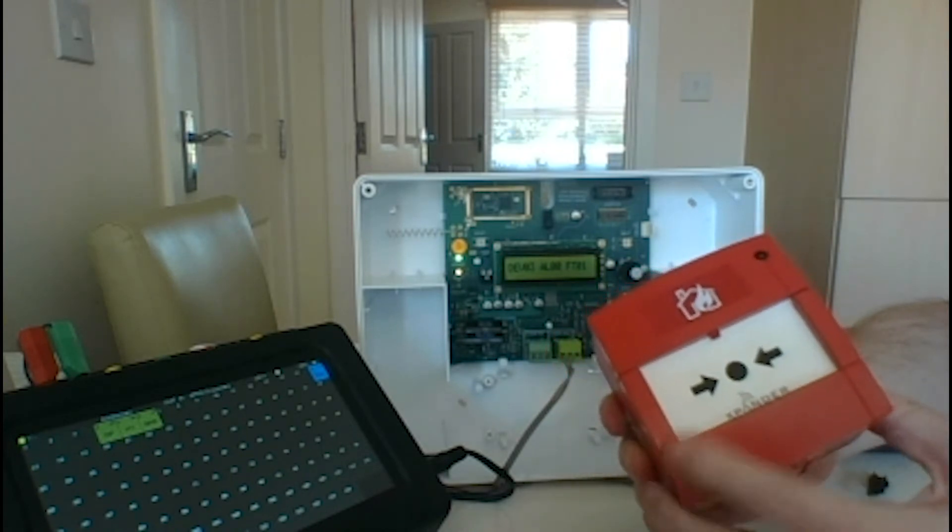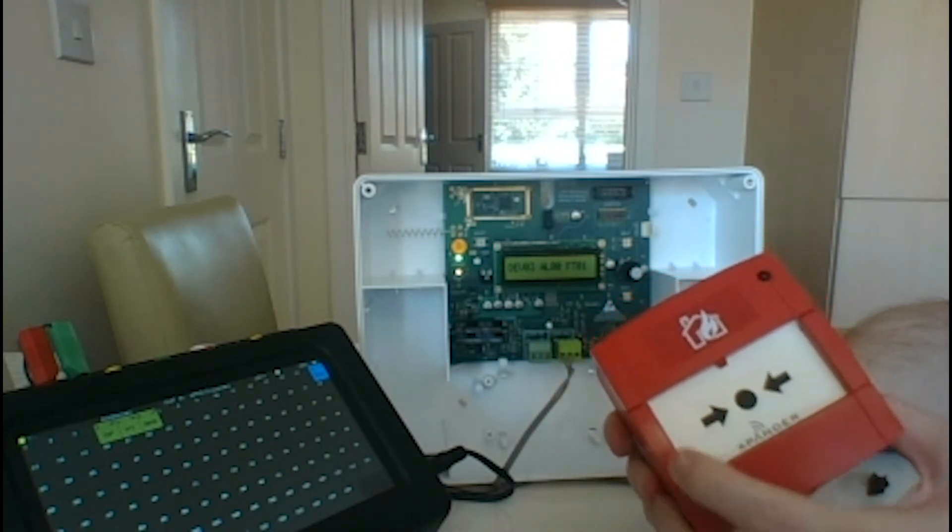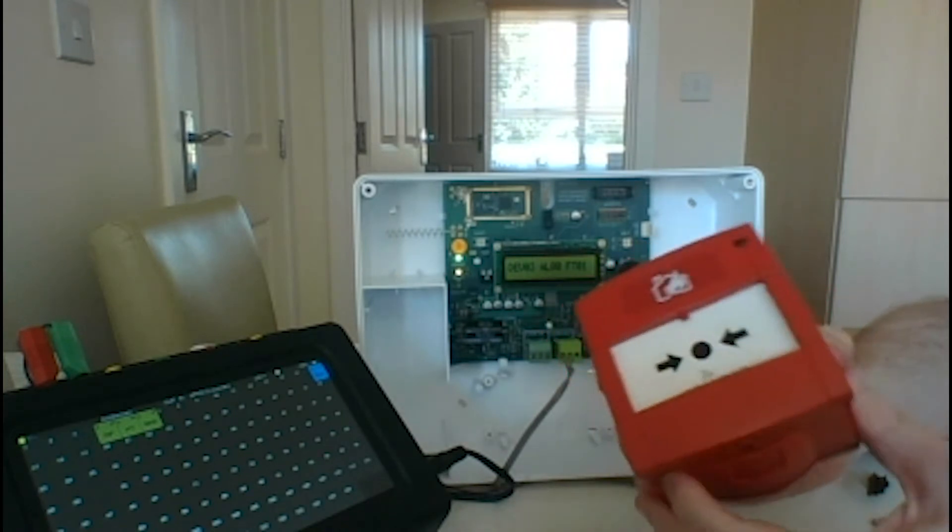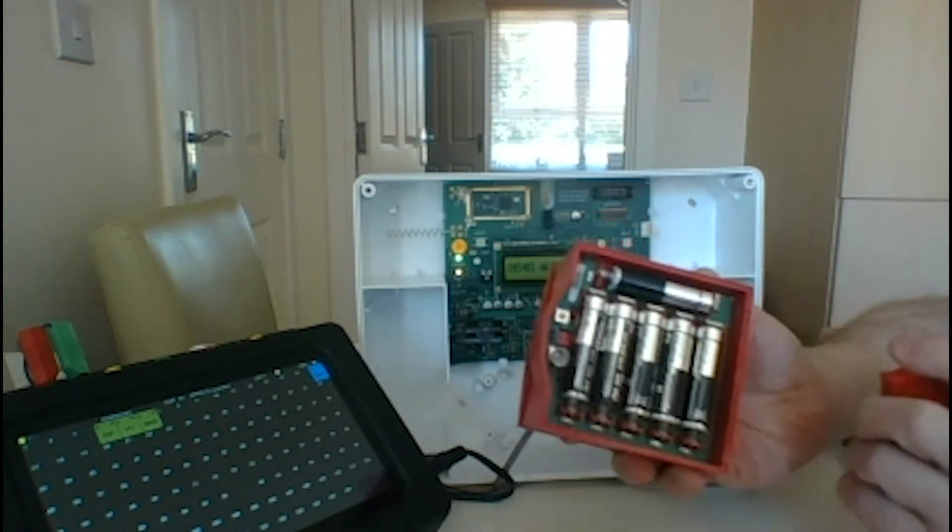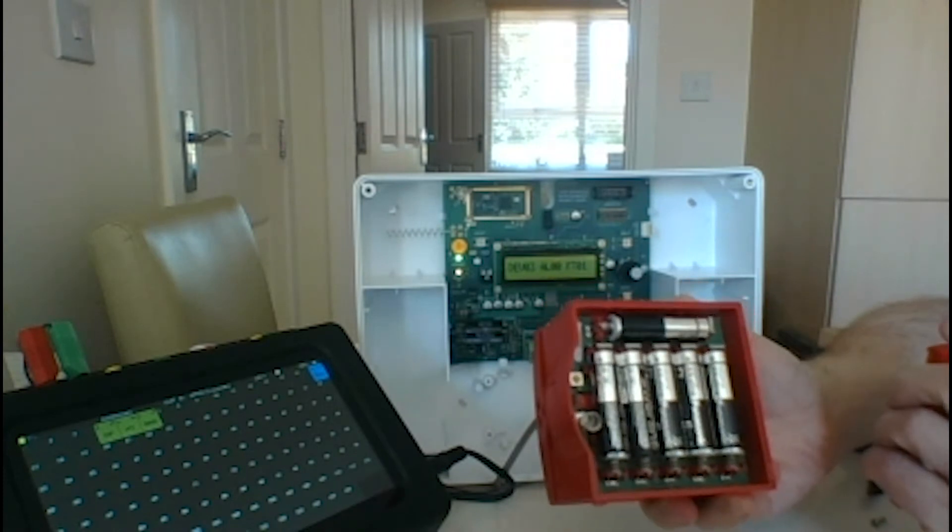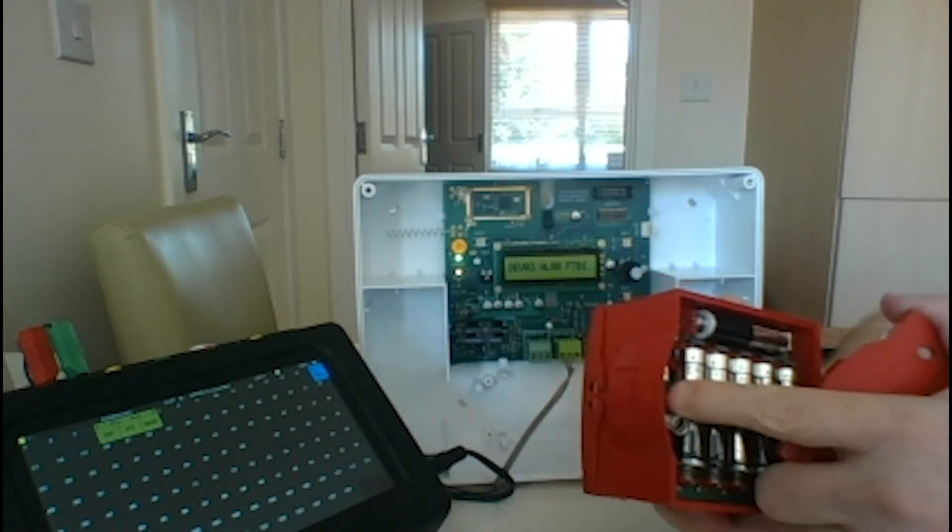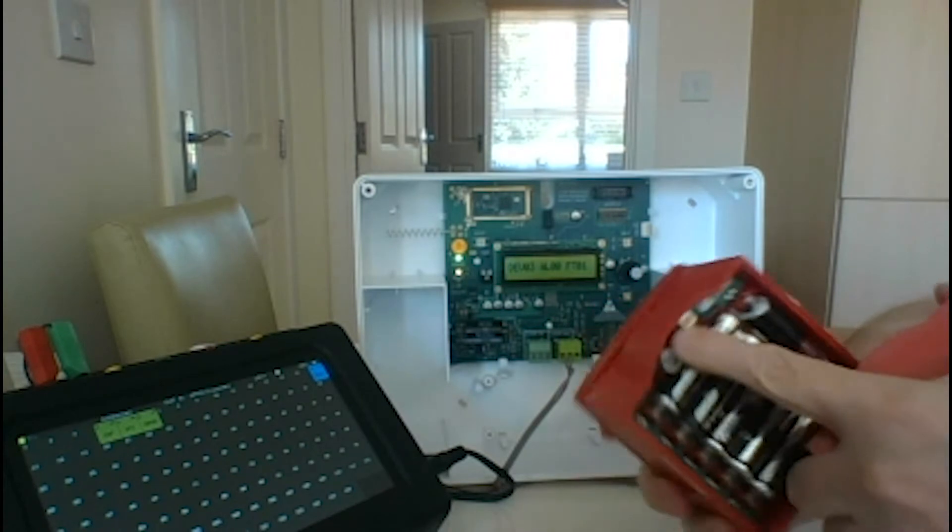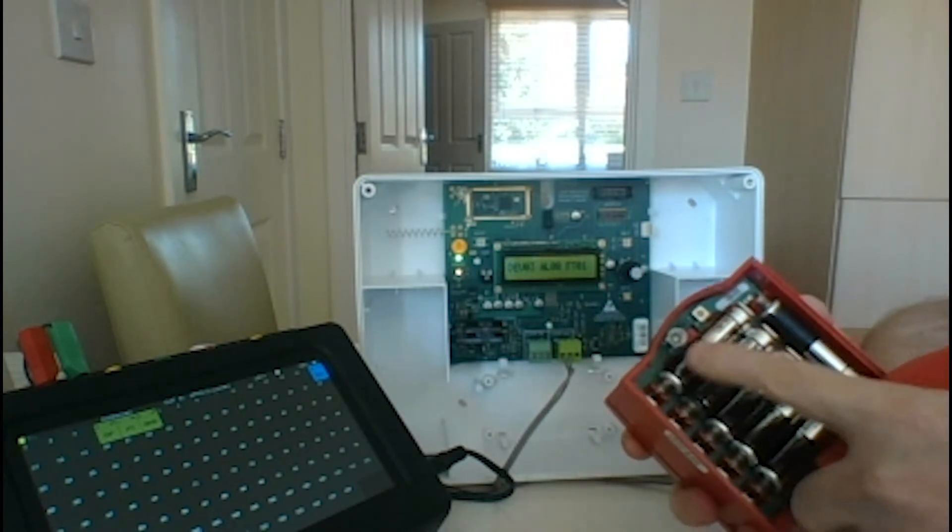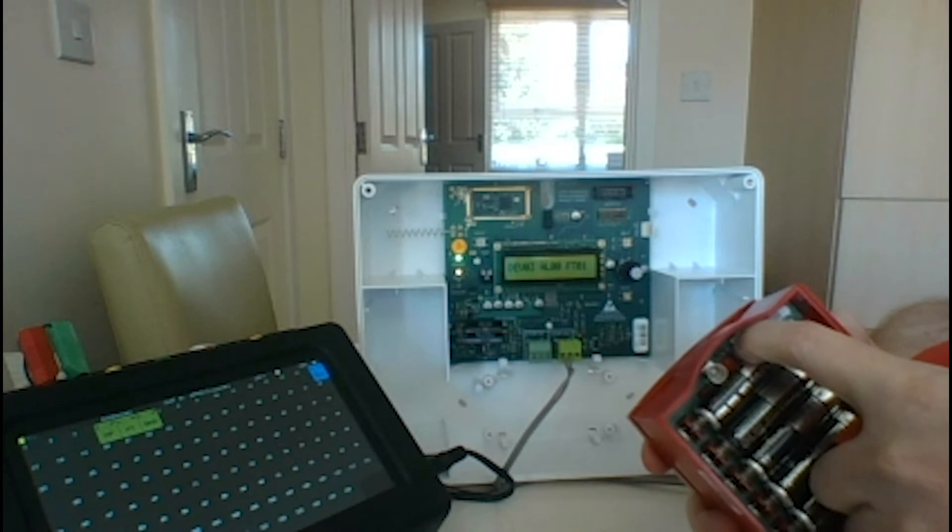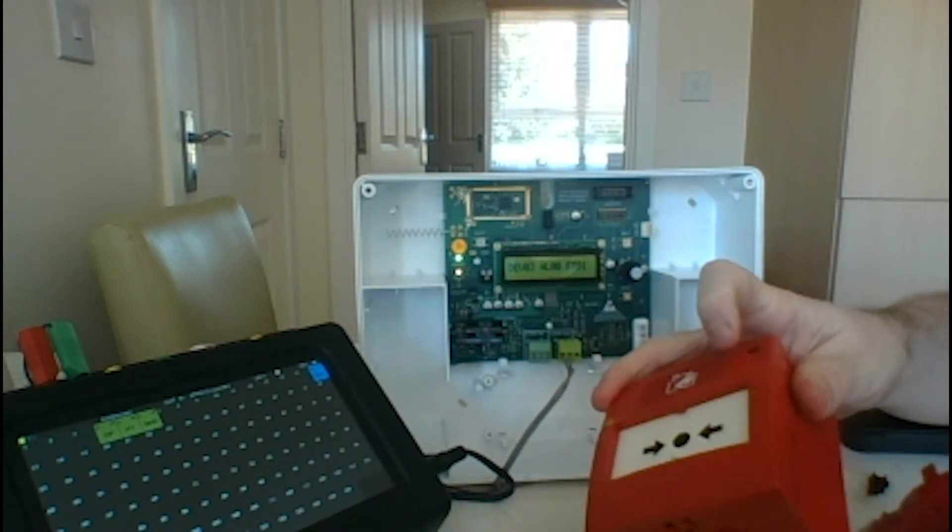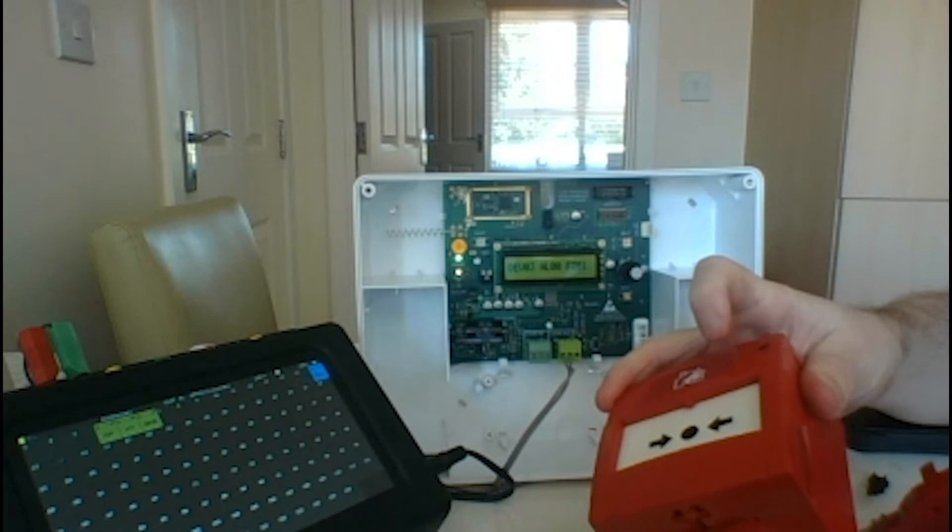This is a KAC MCP. It's just a simple mechanism that we're probably very used to. Looking in the back, we've got six double-A alkaline batteries, and normally our jumper would go here. This is our log on button that we would press. Once we press that, the LED on the front of the call point starts to flash and we could add it to the interface.